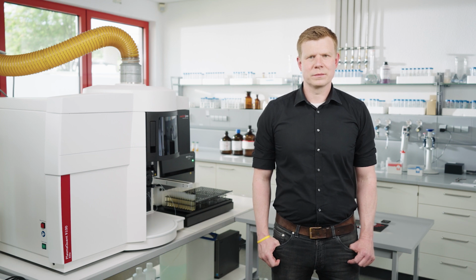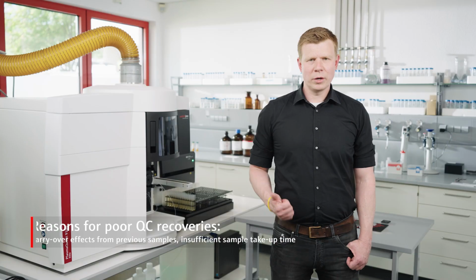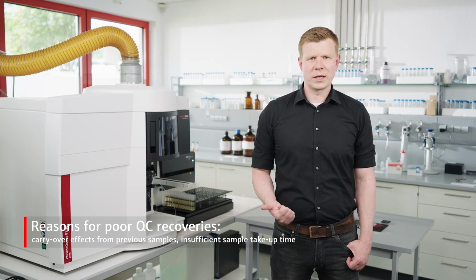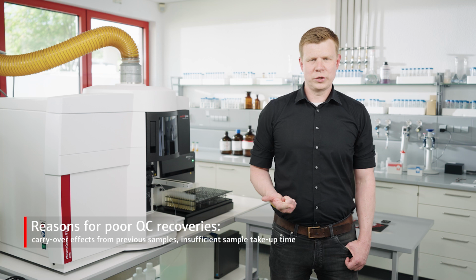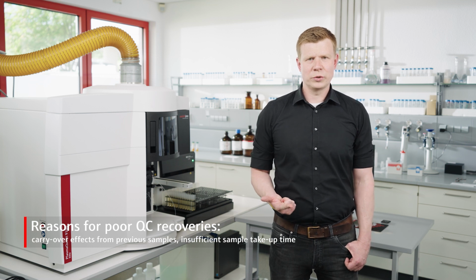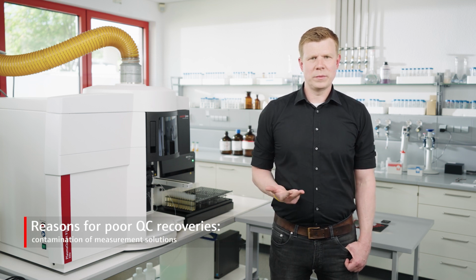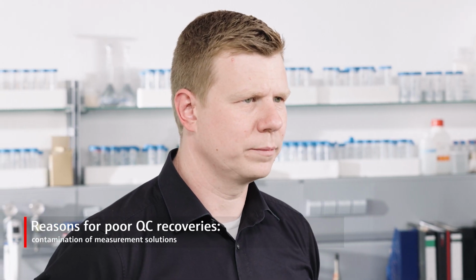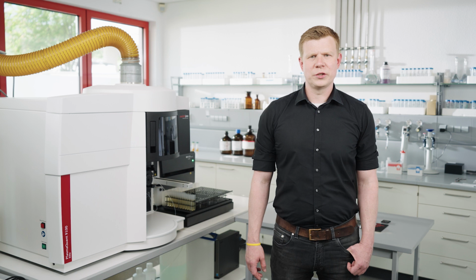The following reasons can result in poor QC recoveries: carryover effects from previous samples or calibration solutions, insufficiently long take-up time of the measurement solutions, or contamination of the measurement solutions from chemicals, vials, or sample tubing. If QC samples are in general not passed, it is advised to review the method settings and the sample preparation procedure. In our measurement, all quality criteria are met and we have successfully finished the measurement.